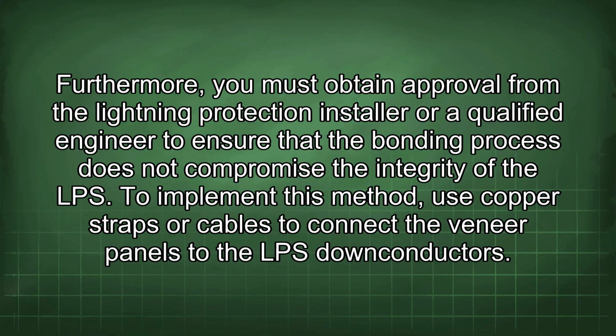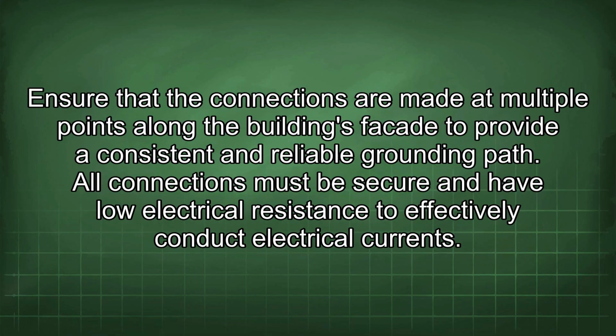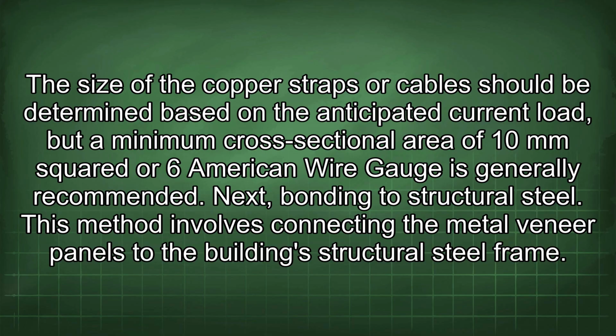To implement this method, use copper straps or cables to connect the veneer panels to the LPS down conductors. Ensure that the connections are made at multiple points along the building's facade to provide a consistent and reliable grounding path. All connections must be secure and have low electrical resistance to effectively conduct electrical currents. The size of the copper straps or cable should be determined based on the anticipated current load, but a minimum cross-sectional area of 10 mm² or 6 American wire gauge is generally recommended.